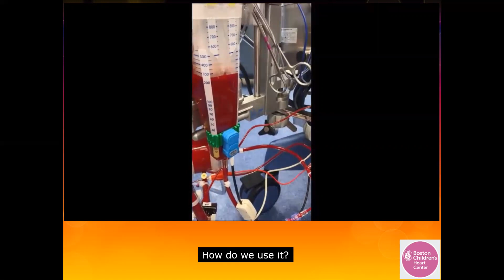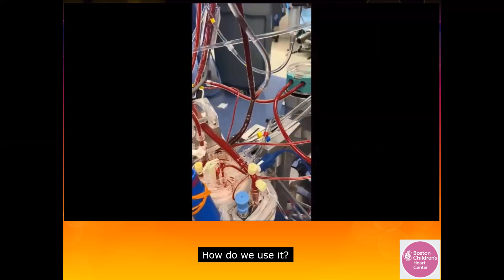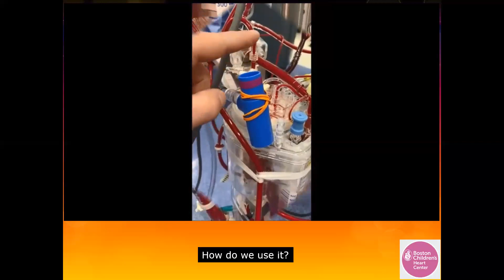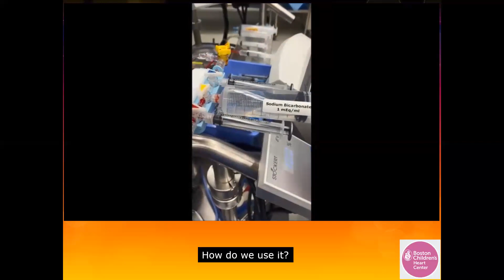The ultrafiltration head is turned on and the ultrafiltrate line is removed. The volume is taken back down to 75 milliliters. As a reminder, the flow path is from the venous line to the ultrafiltrate head to the ultrafilter top, out the bottom, to a stopcock that connects to a line which returns to the reservoir. Once the volume is down, 5 milliliters of bicarb is added, followed by 300 units of heparin and 100 milligrams of calcium gluconate. The ultrafiltration head is eventually turned off and a prime blood gas is sent.